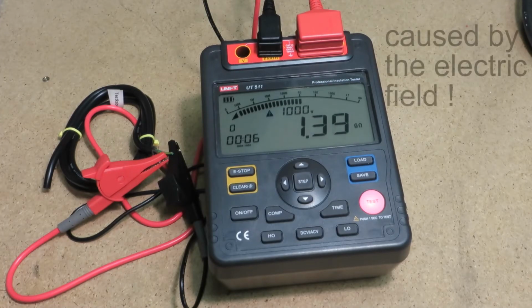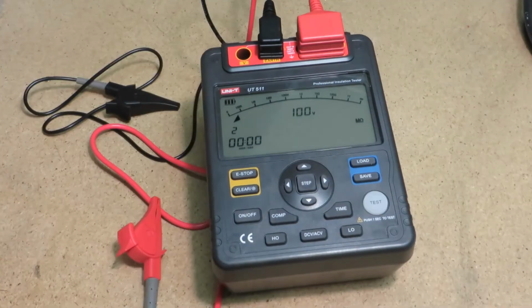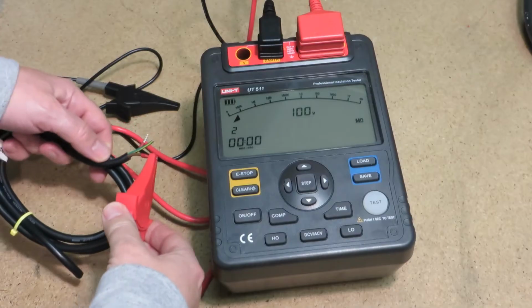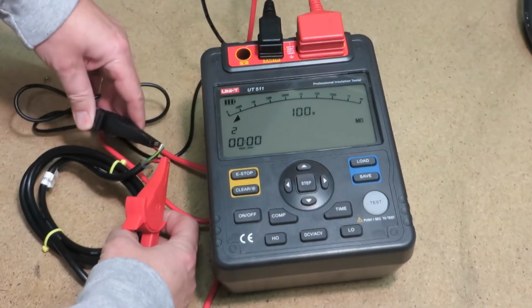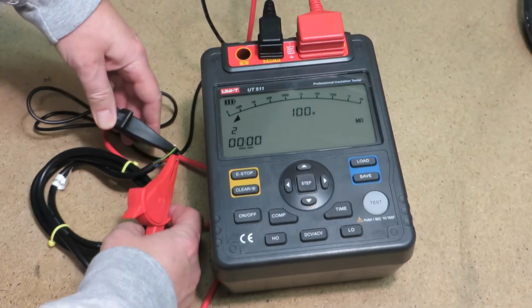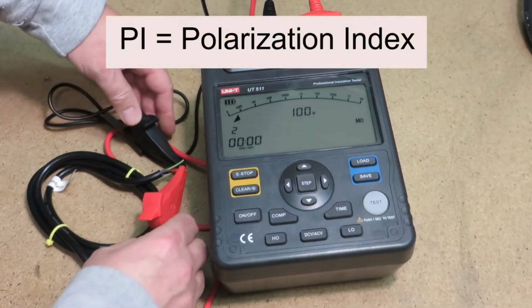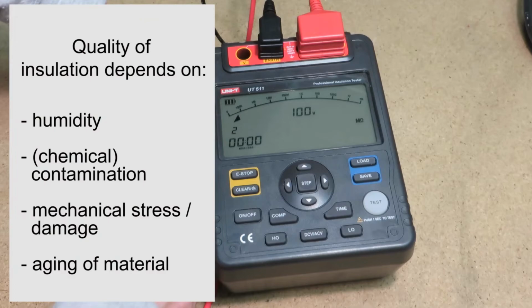The value is rising because of the polarization of the insulating material. Now we want to find out the polarization index Pi of this cable. In short, the polarization index is a value that tells us something about the quality of insulation. It depends on humidity, chemical contamination or mechanical damage, and of course aging of the insulation material. You can find a lot more information about this on the web.